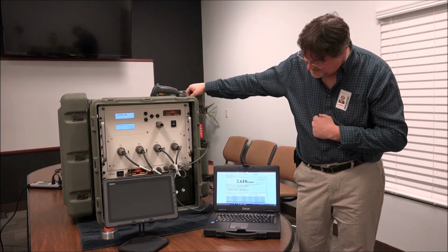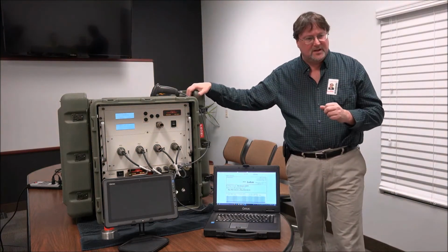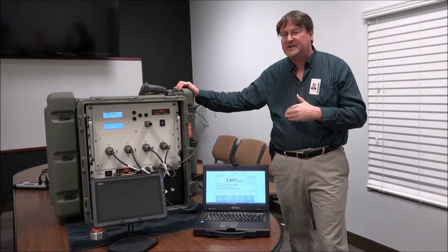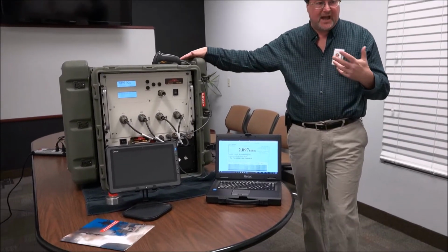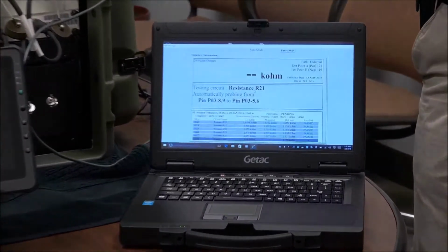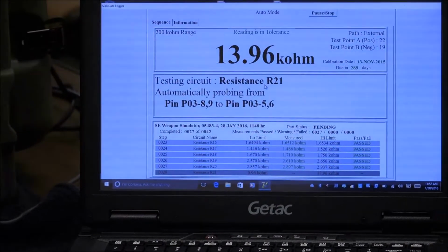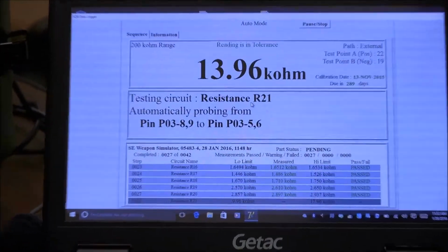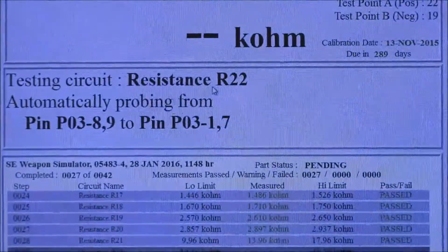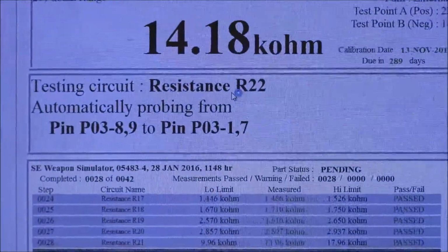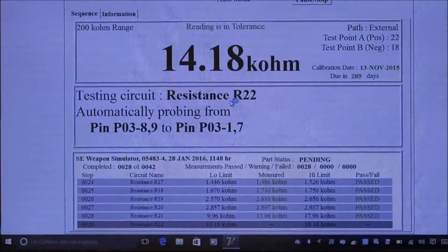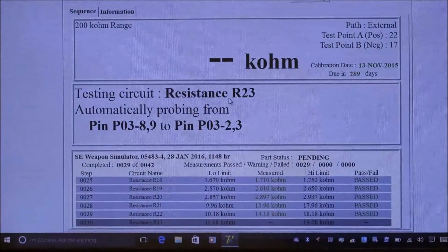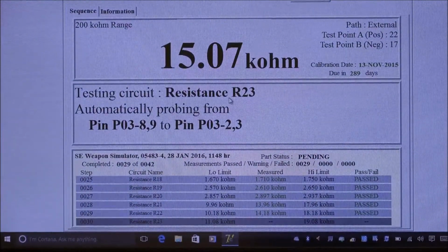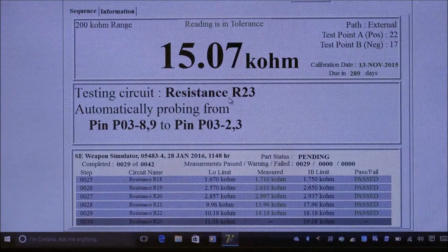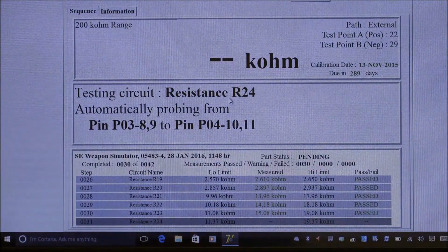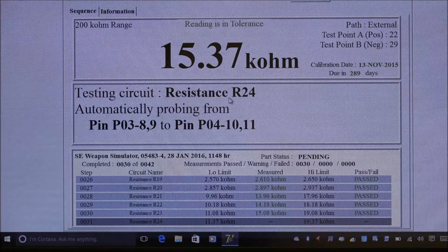The time you see it taking readings is adjustable. We can configure that. We've specifically configured it so that we have some time to talk about how the system is working. So it's got a couple of seconds of data stability and a couple of seconds of data reading. When working with standard circuits that don't have capacitance, you can bring these times down to a second each. With anything that has capacitance, though, you have to keep in mind that you have to wait for the circuit to stabilize as it charges on the test current.